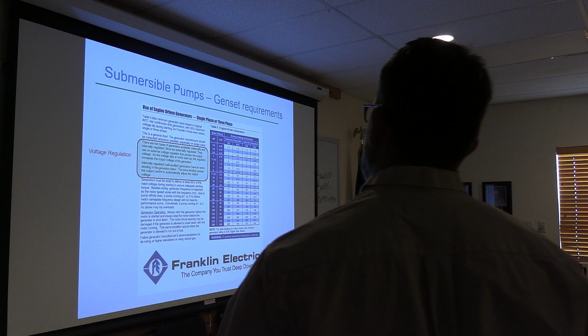Submersibles are built with a thrust bearing. A thrust bearing is a little bit like the regulators. You kind of have to set them. And if you don't start a submersible quickly enough, that thrust bearing won't get the water film between it, and you can start to burn out the pump. So there is a limit to how quickly or how slowly you can ramp a submersible. You need to be mindful that you can ramp it a little bit, but you're going to need to get that submersible to horsepower pretty quickly.